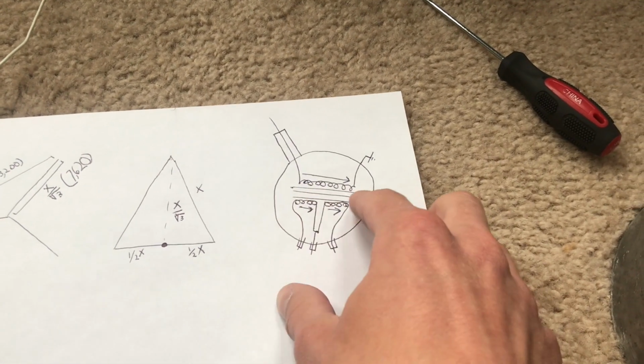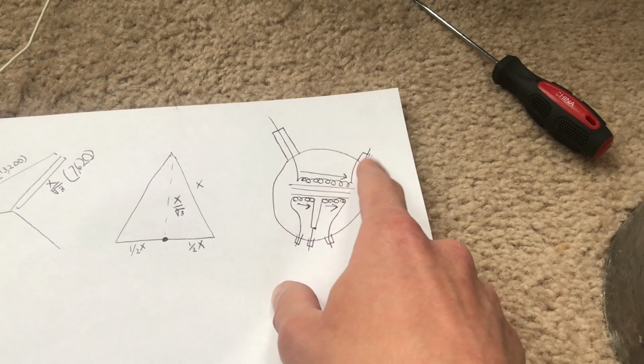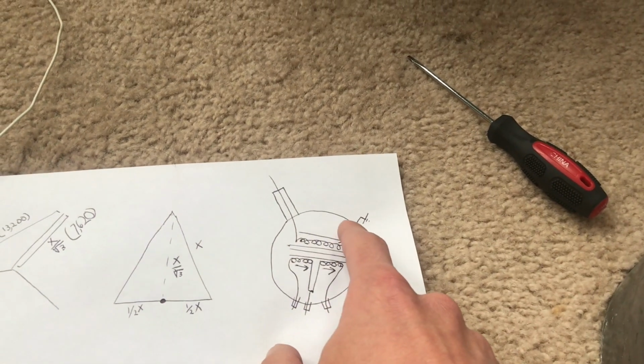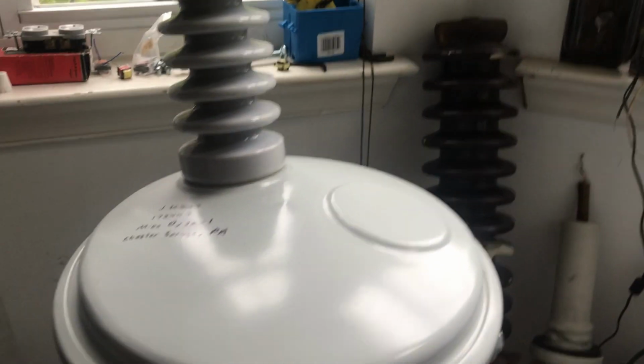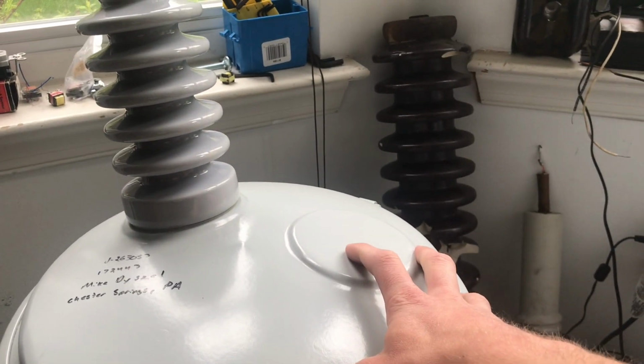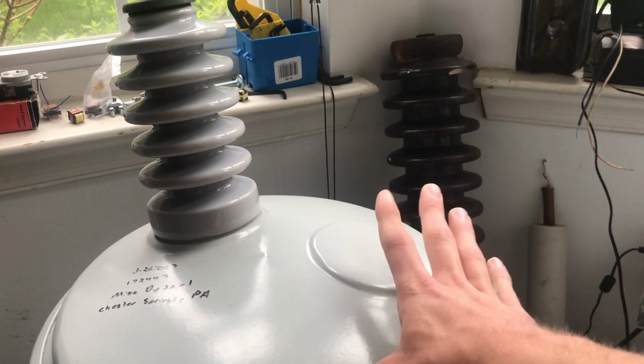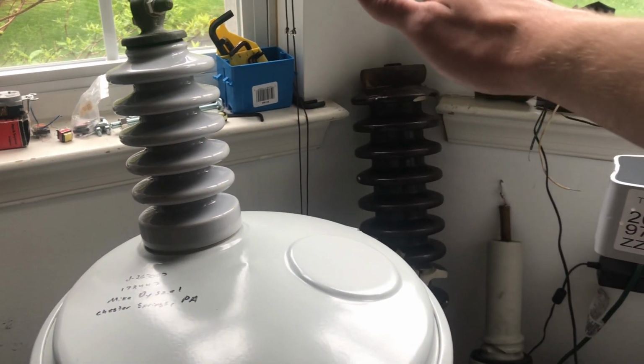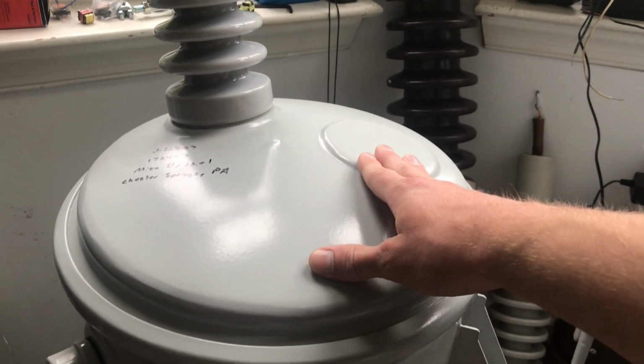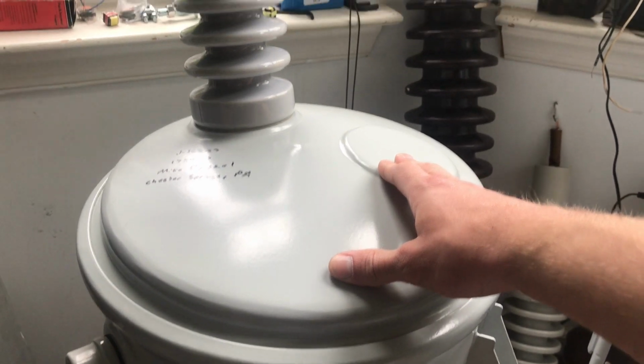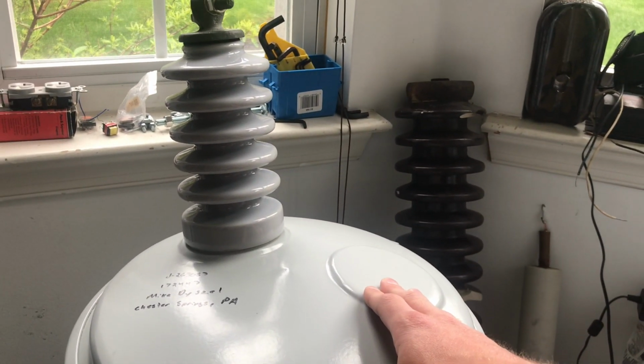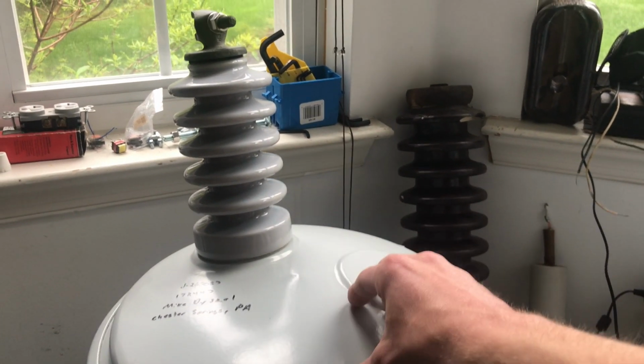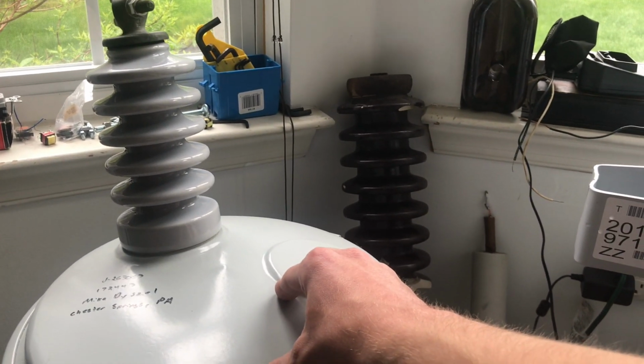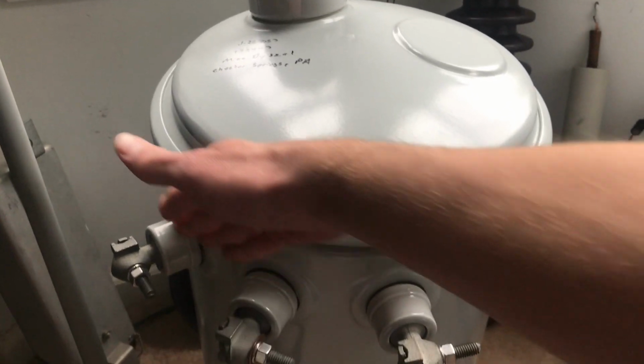Here is just another specification of what's inside the transformers. You can have a dual bushing transformer. So you can see they made provisions for this transformer here in the factory.